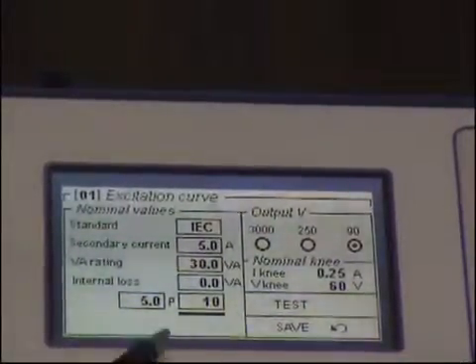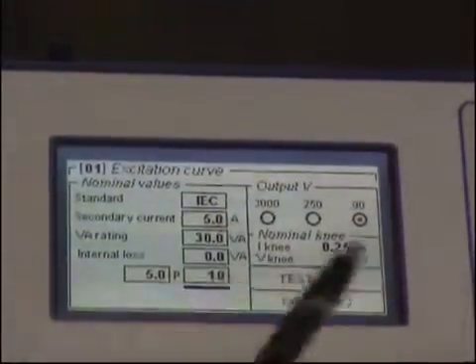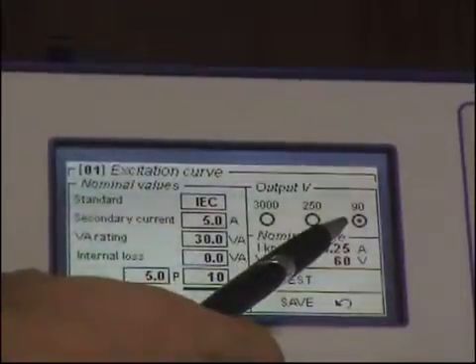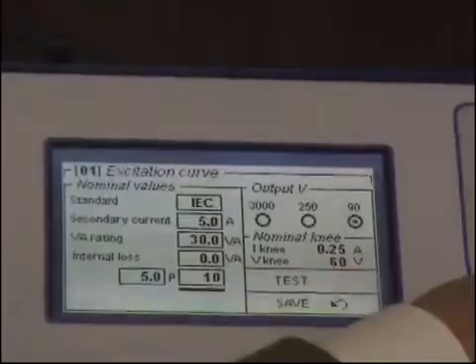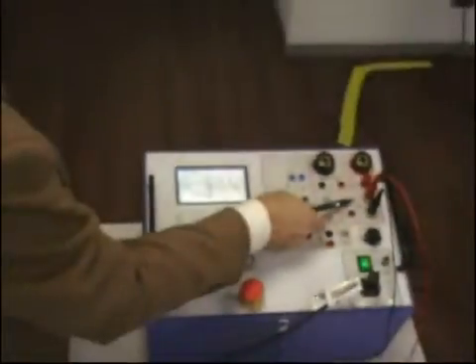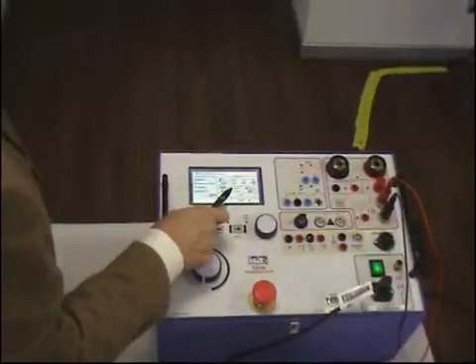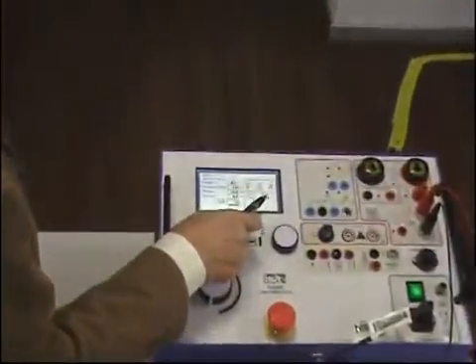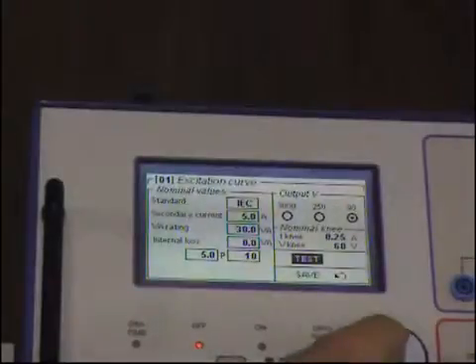As soon as I have entered these values, the test set itself is suggesting to connect to the 90 volts output, and this is where I have connected it — 90 volts. It is telling me that the nominal knee is 0.25 amps and 60 volts. So I have connected, and I go to test.